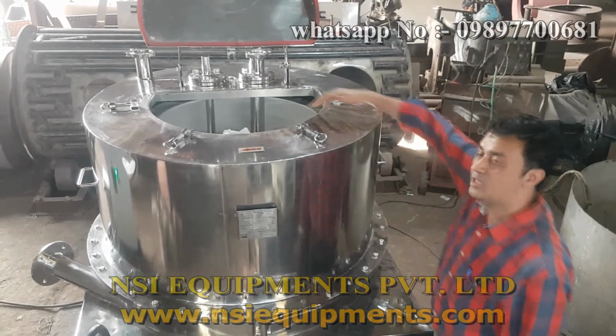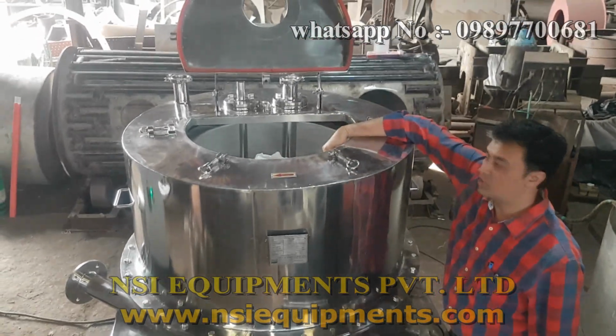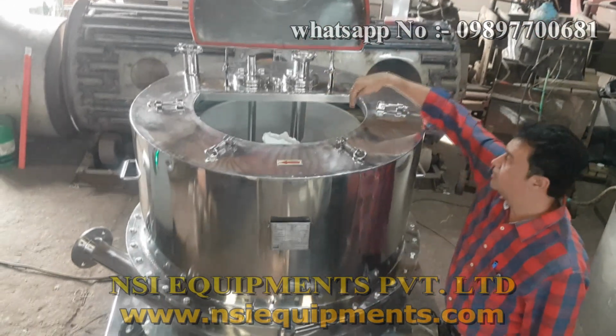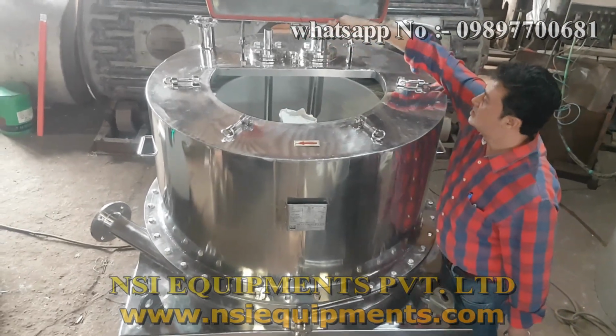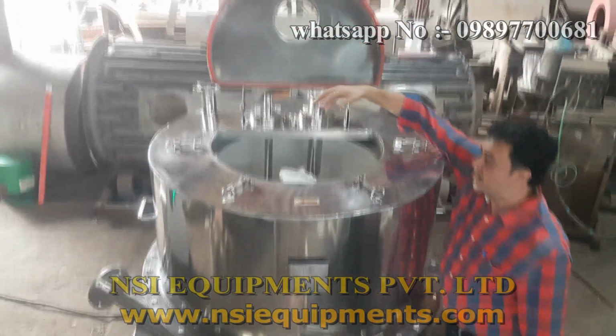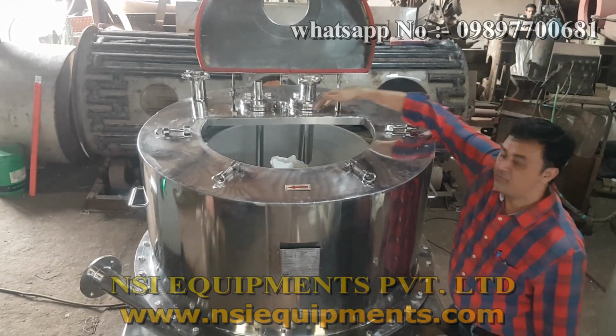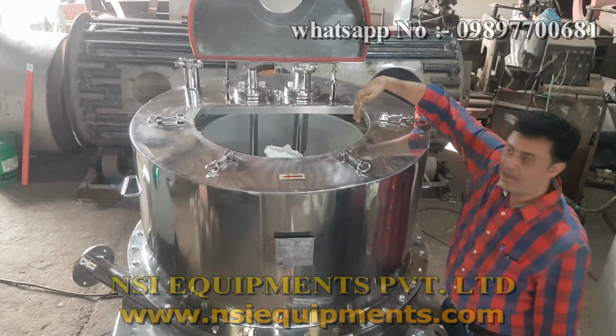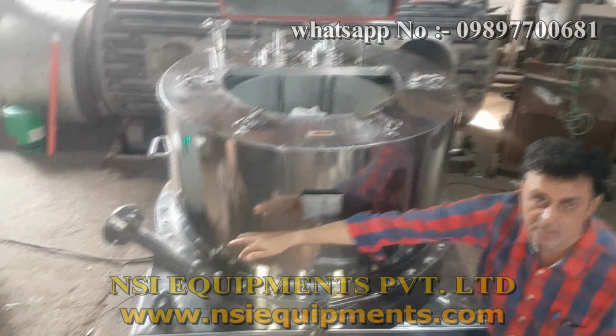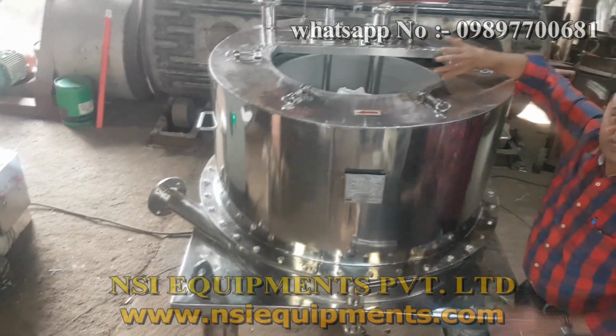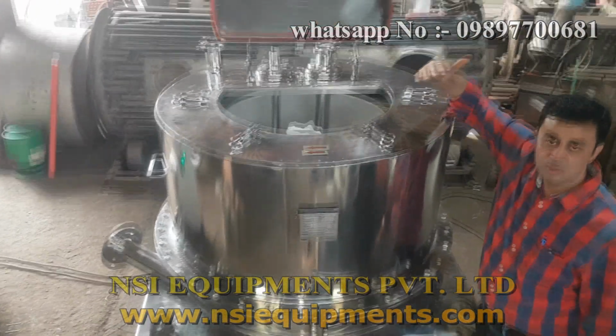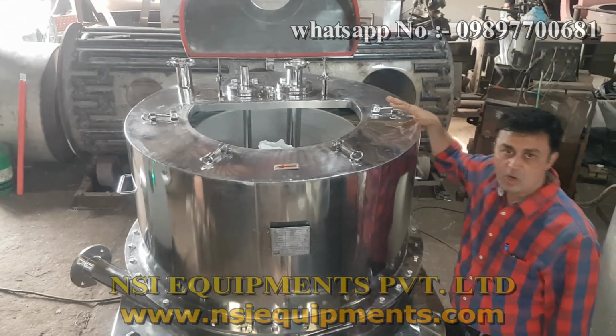Now you can see the basket of the centrifuge. This is the rotating basket of the centrifuge with a filter bag. And you can see the nozzles. This is the feed nozzle, this is the wash nozzle, and the material is fed from here. It forms a cake with the basket, and the mother liquor goes out from the outlet nozzles. After the centrifuging is done, material is scooped out from the top. This is the top discharge model.